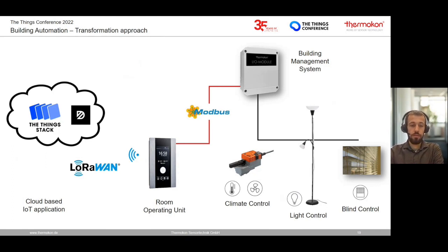On the other hand, if we go the way back from an IoT portal like DataCake, through a network server like The Things Stack, to our existing system, we can realize override functionalities - we can control the room from the cloud. But the existing building management system stays as it is. You don't have to change the components, and we don't have to allow direct access to the building management system. You're just adding the LoRaWAN functionality, and the whole setup on the building management side stays as it is.